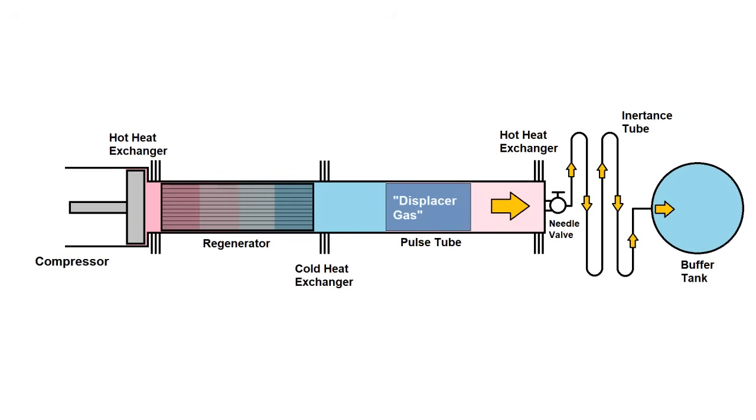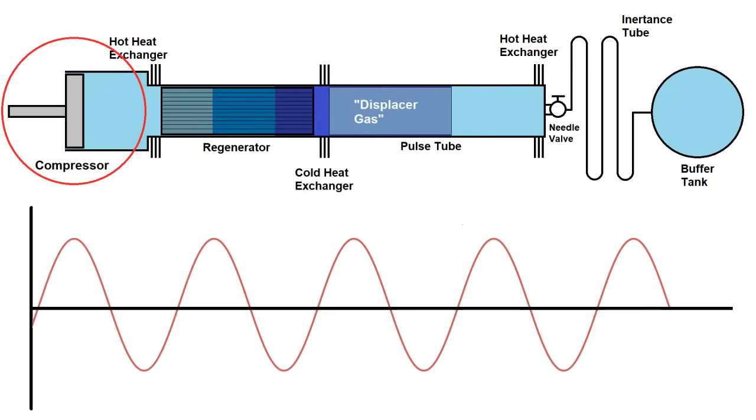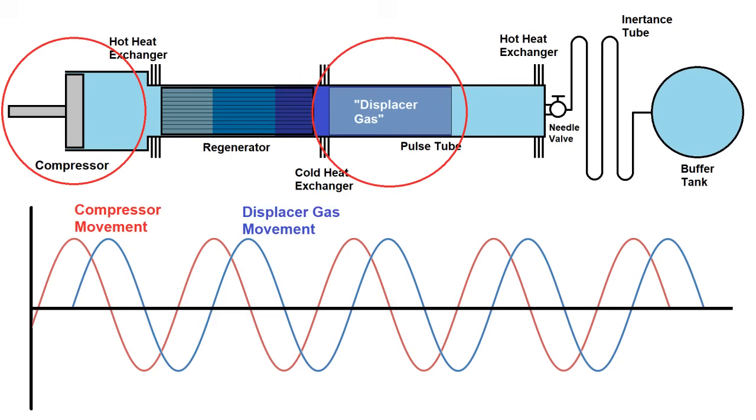This pressure causes the gas in the right side of the tube to accelerate through the needle valve and into the buffer tank. Now the compressor moves back and starts expanding the gas but the displacer gas is still moving to the right from its momentum so a net cooling effect occurs before the displacer gas can make it back to the other side of the pulse tube. If this is the compressor movement and thus pressure this is what the movement of the displacer gas would look like in the pulse tube. The combination of the so-called inertance tube and buffer tank creates a phase shift that causes gas flow to lag behind pressure by around 60 to 90 degrees which is about the same phase shift as a displacer piston would have in a Stirling cycle cooler.